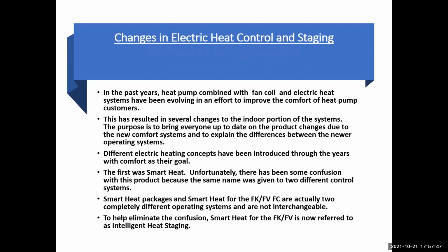Changes in electric heat controls and staging. In the past, heat pumps combined with fan coils and electric heat systems have been evolving in an effort to improve comfort for heat pump customers. This has resulted in several changes to the indoor portion of the system. The purpose is to bring everyone up to date on product changes due to the new comfort systems and to explain the difference between the newer operations. Different electric heat concepts have been introduced through the years with comfort as their goal.